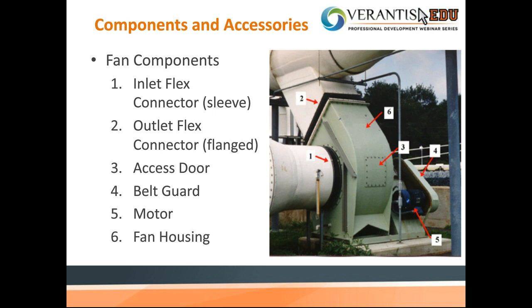Number 4 is the belt guard we talked about on the Arrangement 9 style fan. What you can't see in this picture is the actual shaft guard, but anytime there is a belt guard, there is inevitably going to be a shaft guard that goes with it. Number 5 is the motor, and that motor is sitting on an adjustable base. And then number 6 is the actual housing that the impeller lives in inside of the fan.